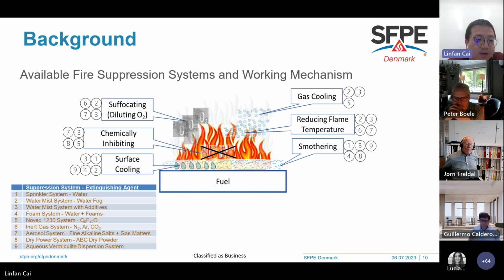I also categorized the working principle of each system. For instance, number 3, the water mist system with additive, has the function of gas cooling, reducing adiabatic flame temperature, smothering - meaning when a lot of water condensation is deposited on the surface, it covers the fuel surface - also surface cooling, chemical inhibiting, and suffocating. I use this as an example because water mist with additive has all the functions of fire suppression, which I'll explain later. Also, literature results from researchers suggest water mist with additive could be considered one of the most effective extinction agents so far.